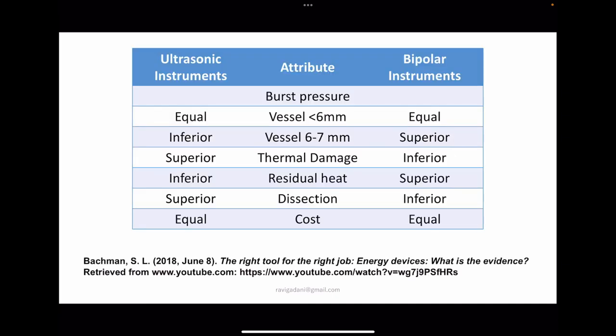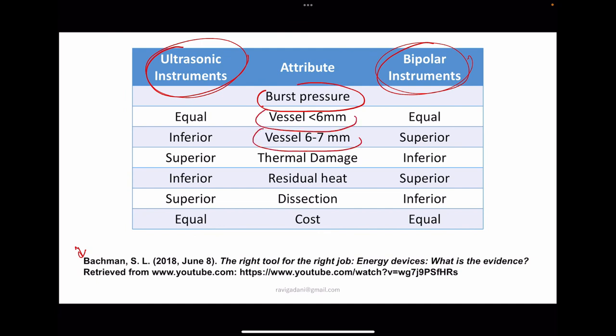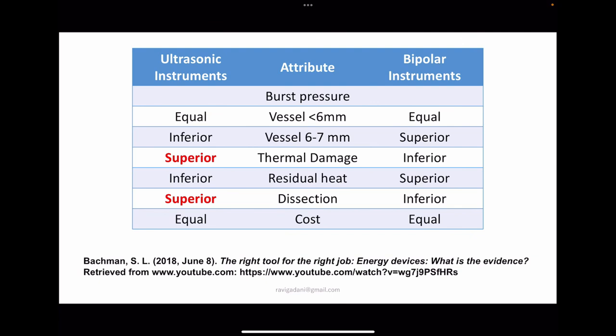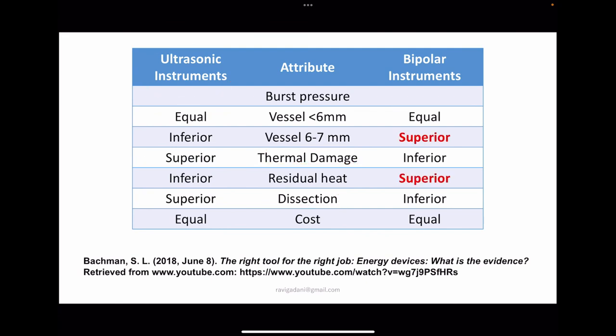A comparison between ultrasonic and modern bipolar instruments: regarding thermal damage laterally and dissection capability, ultrasonic instruments are superior. But for vessel sealing of 6–7 mm vessels and for lesser residual heat, bipolar instruments were superior.